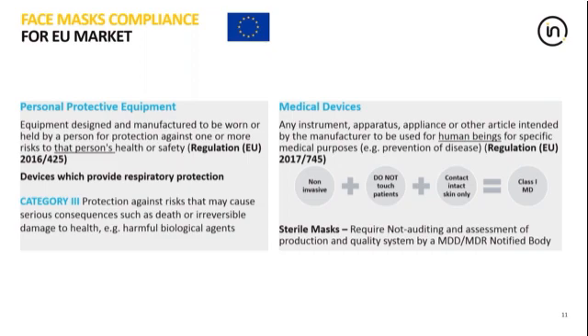This slide shows the certification routes for the masks in Europe. Medical masks are considered to be within the scope of the Medical Devices Directive, which is legislation which will be replaced by the Medical Devices Regulation. Masks, for medical purposes, are first of all non-invasive. They do not touch a patient during a surgical procedure and are only in contact with the skin. So this makes them a relatively low risk medical device, and they're considered to be a class 1 medical device.